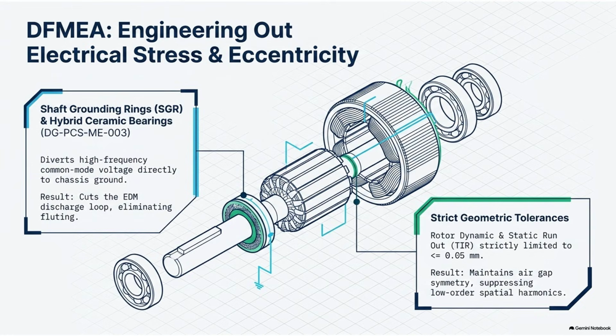Okay, how does an SGR work? Well, the core problem with the EDM bearing current is that the electricity has nowhere else to go. The path of least resistance is straight through the lubricating oil to the grounded casing. Right. So the engineers simply provide a better path. An SGR is essentially a highly conductive ring fitted with a carbon brush that physically rides against the spinning motor shaft. Because carbon is highly conductive. Yes, and it can handle the friction of a shaft spinning at 12,000 RPM without wearing away too quickly. It uses a small spring to maintain constant physical contact.